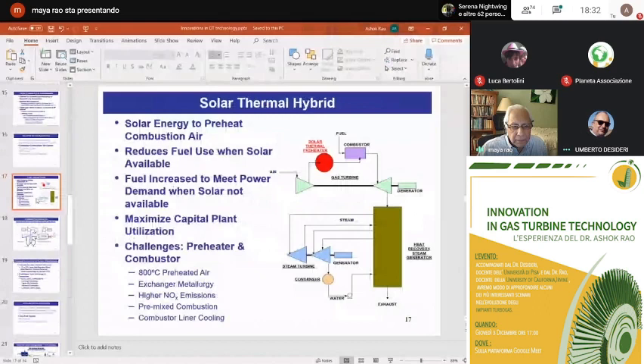Yeah, especially if the gas turbine trips, then you have this huge amount of air capacitance sitting there, and you'll have to quickly vent it before it starts, otherwise it'll keep spinning the turbine. You're right, and you have to have very high, very fast-acting valves to dump this hot air to the atmosphere.